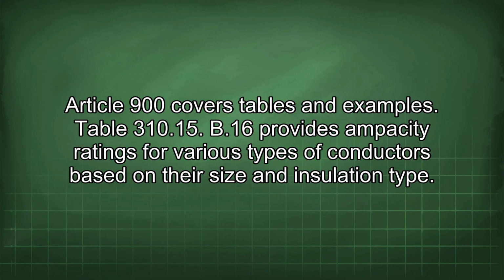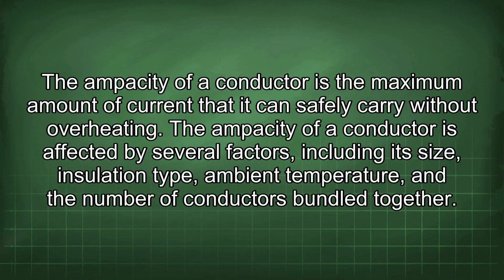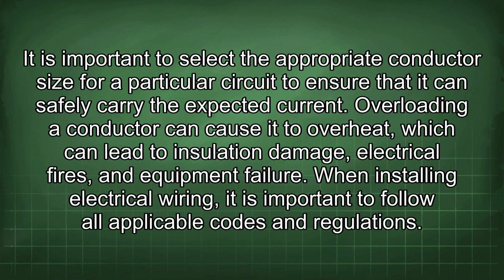Table 310.15(B)(16) provides ampacity ratings for various types of conductors based on their size and insulation type. The ampacity of a conductor is the maximum amount of current that it can safely carry without overheating. The ampacity of a conductor is affected by several factors, including its size, insulation type, ambient temperature, and the number of conductors bundled together. It is important to select the appropriate conductor size for a particular circuit to ensure that it can safely carry the expected current.